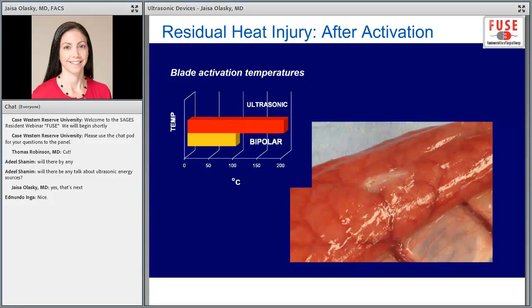And what you're seeing in this slide is an example of injury to the bowel that occurred because these devices are frequently used for dissection, and they're very good at that. Unfortunately, the user has to remember that the actual active jaw stays very hot longer than with other devices. So from 20 to 45 seconds after activation, this device tip, the active jaw, can still be extremely hot.